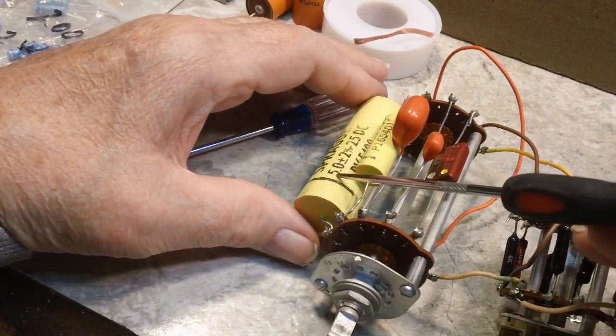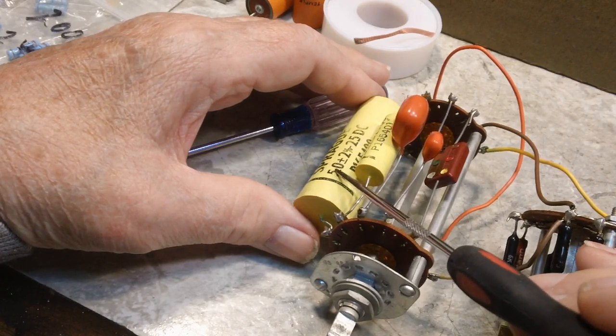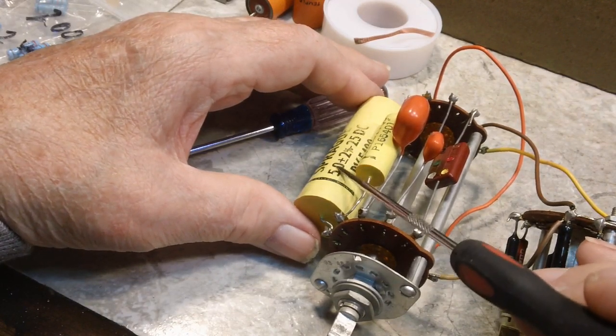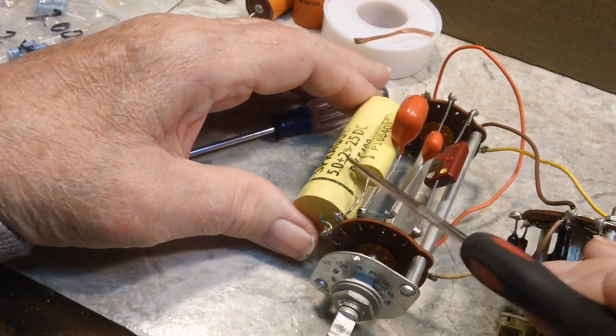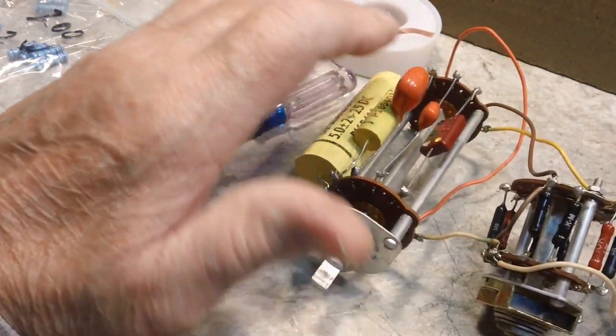All those checked within tolerance. The measurements, I measured them on two different instruments, the component tester and my meter, my DMM. Both put it in within tolerance, the 2% that it need to be. And so those are good.